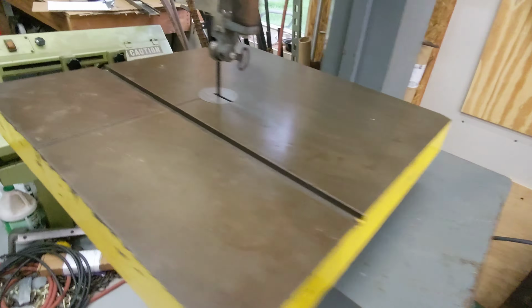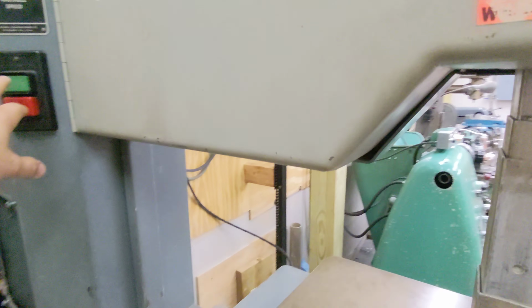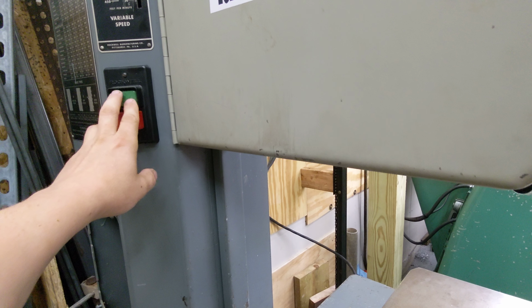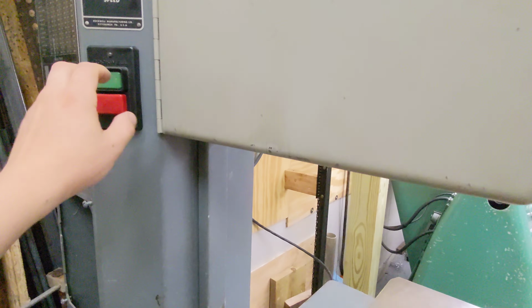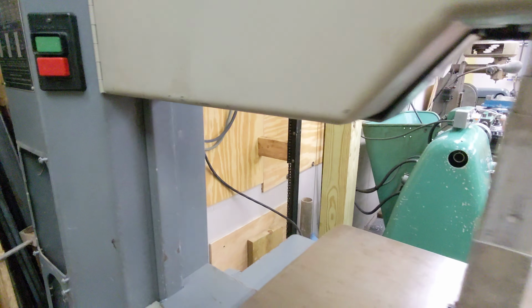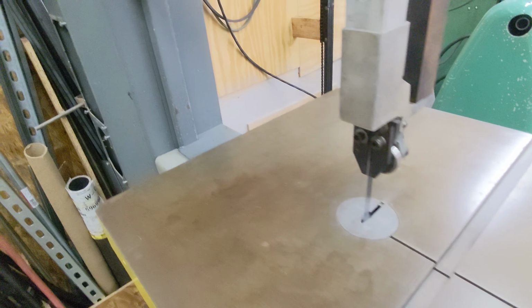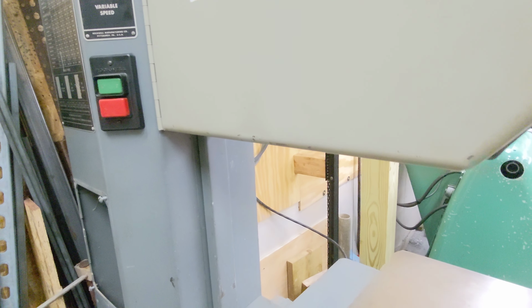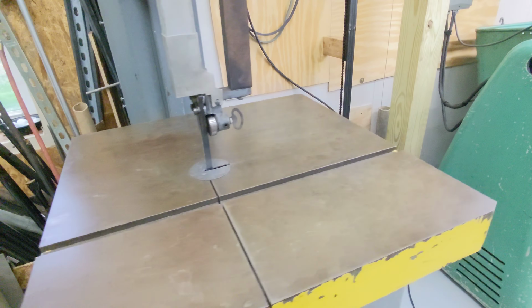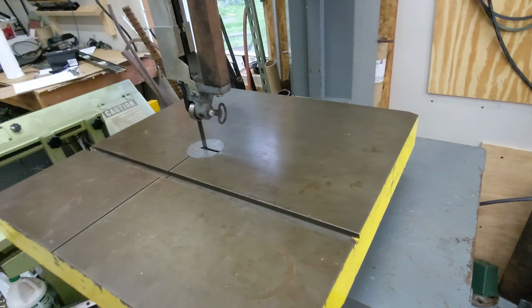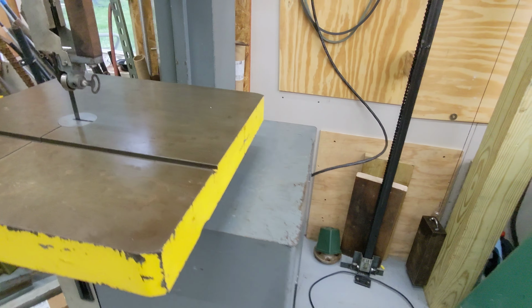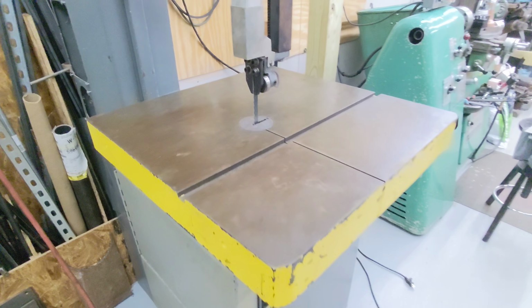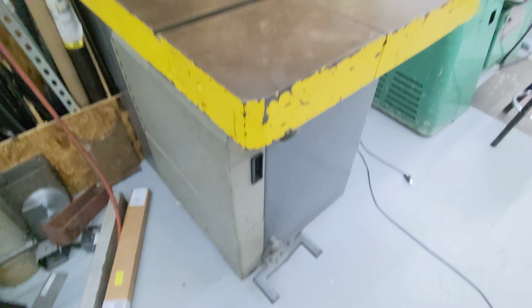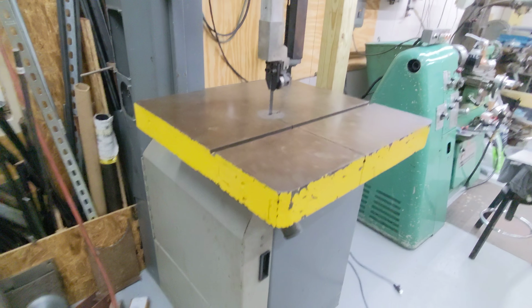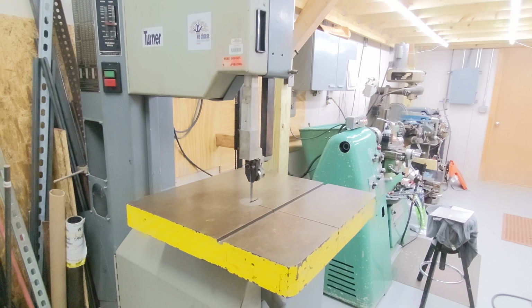So this way, when we start it, all this is going to do is use the higher voltage to latch the contactor, and then close those two 18 gauge wires going to the VFD. And then the stop button breaks the 208 to the contactor coil and opens those 2 wires, which is the stop signal for the VFD. I don't think I'm going to be using it for speed control at all. It's really just for power conversion and soft starting. The variable speed in this machine seems to be in decent working order, so that's all I need the VFD to do.